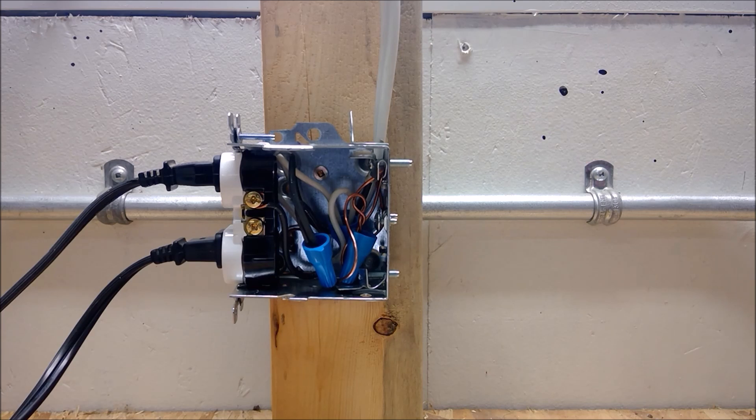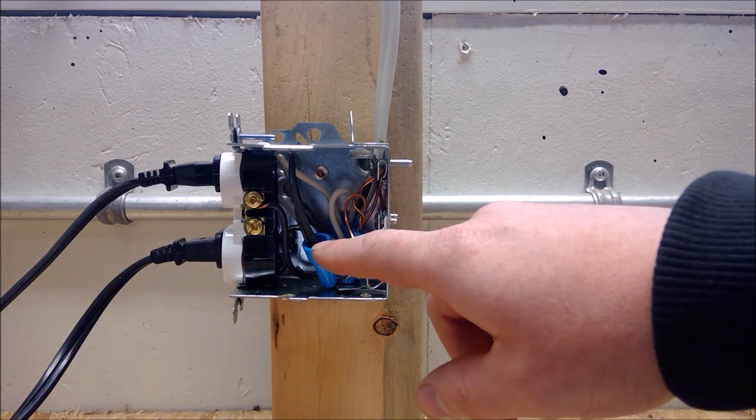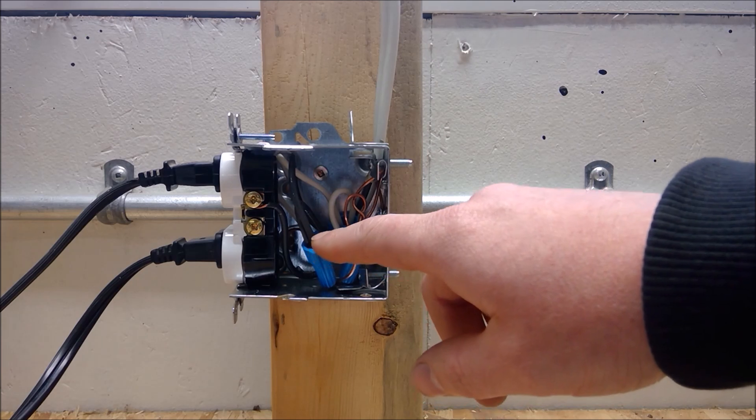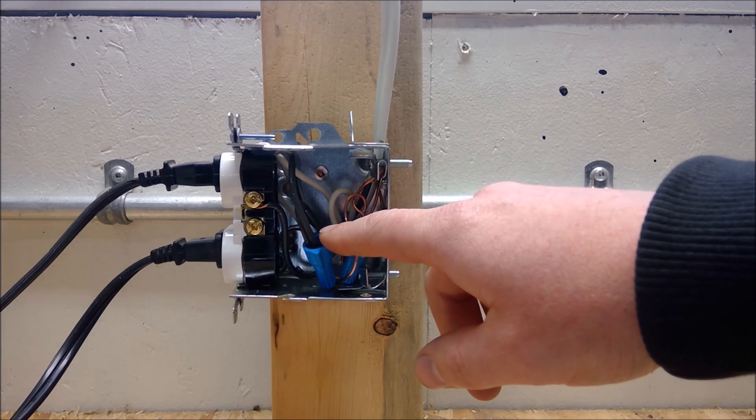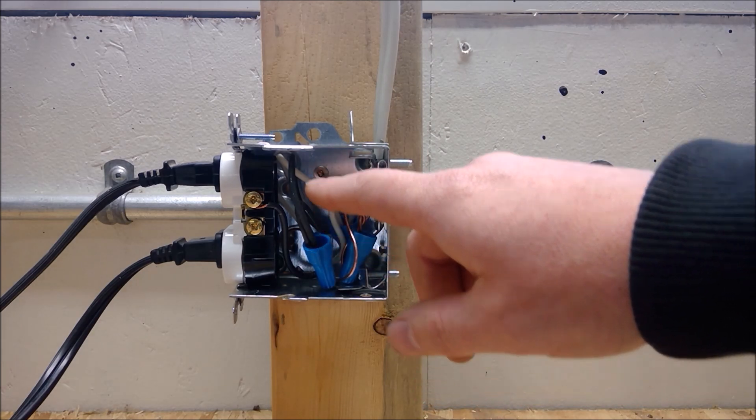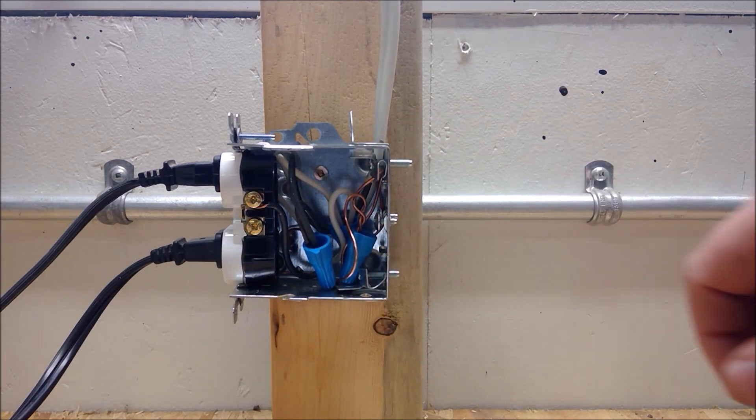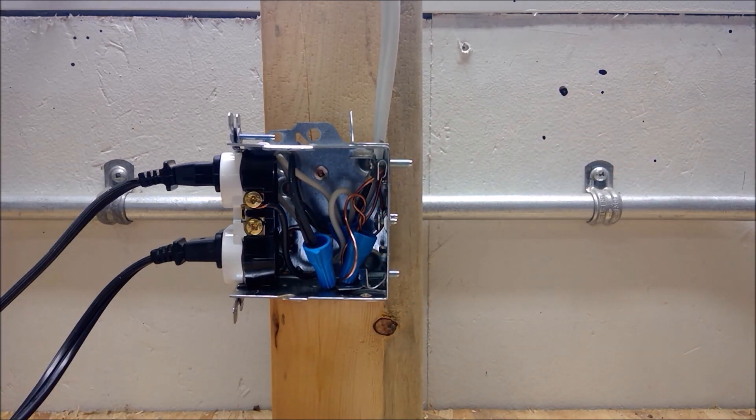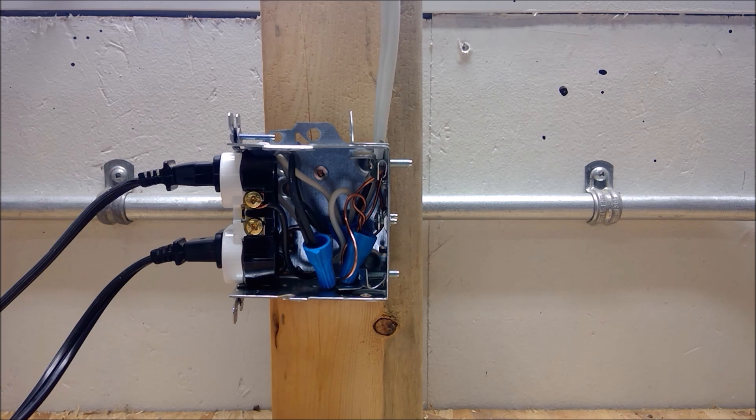This receptacle is wired according to the Canadian electrical code. Unfortunately, what we can't see here is that this connection right here is faulty. These two wires have not been spliced together appropriately and are not making a solid mechanical connection.